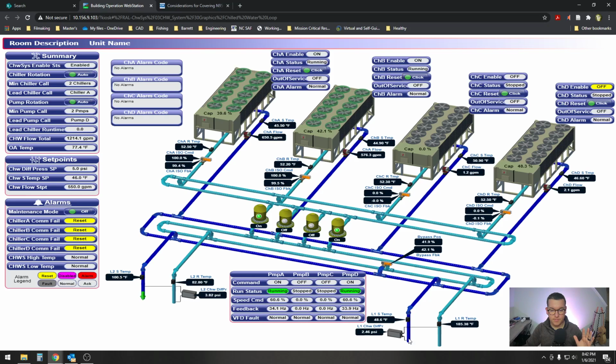Actually, it operates off 2 sensors. I was going to explain that later, but it's more important now. There are 2 sensors in the system for redundancy. It's going to choose the lesser value. So now that this one's higher, we're going to work off this one. Normally it's loop 1 that's always lower. Sometimes it's loop 2, so you just have to pay attention to that. Again, the software chooses the lesser of the 2 to operate off of. So now it's 5.8.